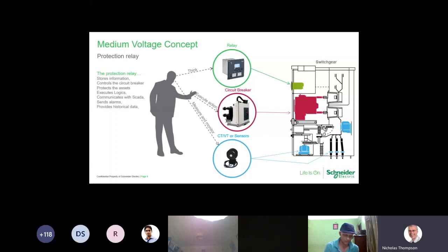Protection relays are quite sensitive instruments. They don't like very high currents, and they certainly don't like very high voltages. And the stepping down from the high voltage and the high current is a safety aspect for the end user at the end of the day. What you don't want is your finger anywhere near anything above a few amps or a few milliamps, and you certainly don't want your finger anywhere close to 11 kV. And the box, the compartment in the switchgear where the protection relay will sit, is quite often referred to in the industry as the LV box. It literally does not have high voltage in there as defined in the 18th edition, and it certainly won't have any high currents that you would associate with the primary circuit.